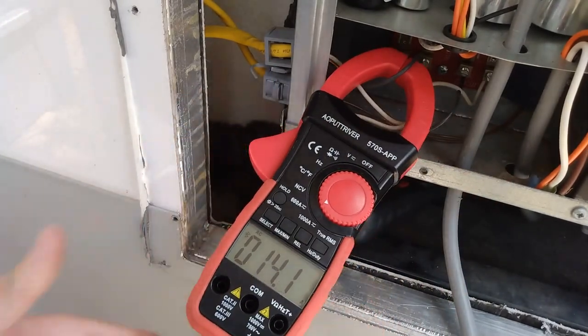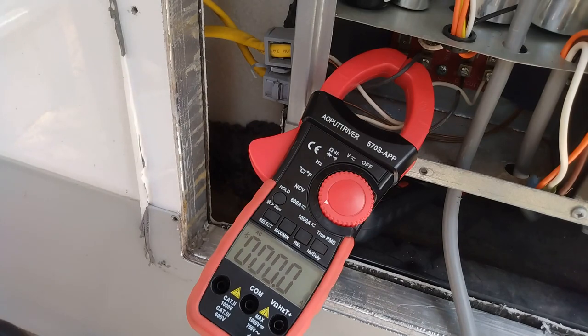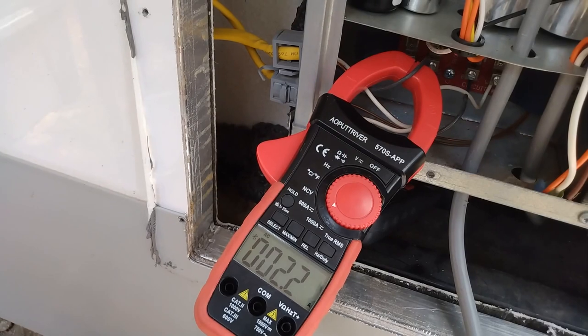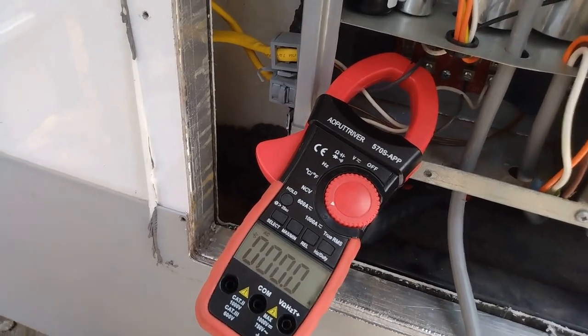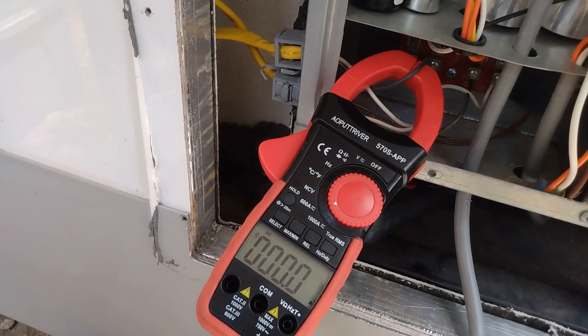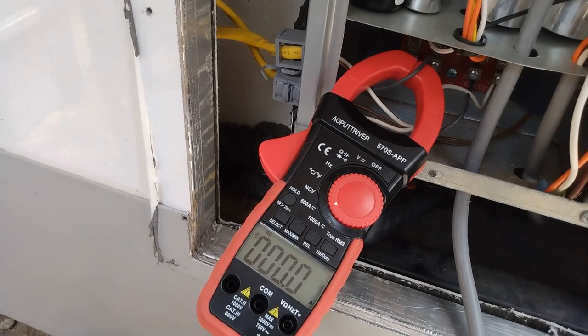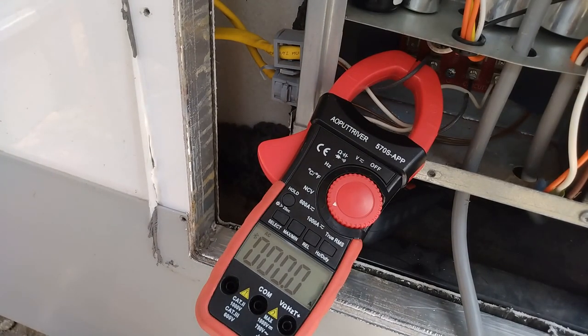Compressor two. Compressor 1, 15 amps. Turn it off, and we'll start it again. On a positive note, the red error light on the control board is not blinking yet. I could have sworn this EasyStart had an LED light in it. It's like an error, unless it's the Bluetooth one. Alright, while we're letting that reset, we're gonna start it again. Amps right now.